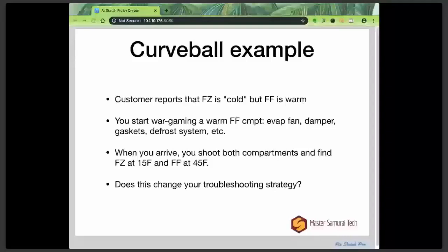You can look at the condenser temperature split, assuming that your condenser is clean, your condenser fan's running, yada yada, right? We know the drill. You can look at the condenser temperature split, and that is the temperature of the saturated zone of the condenser minus the ambient temperature. That's called the split. And that's by design 30 degrees. Anything above 20 is probably okay. Doesn't mean that necessarily the sealed system is quote good, but it's a screening test.